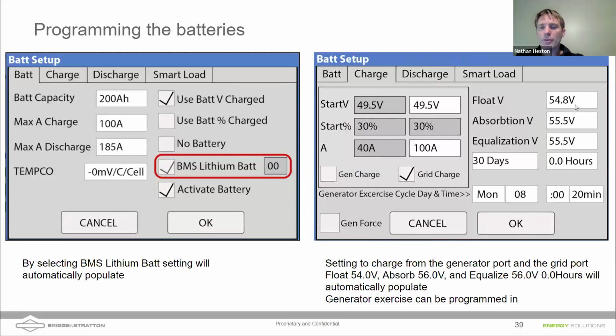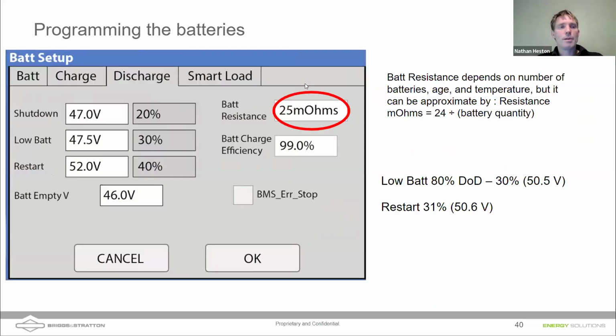Float for our batteries should be 54, absorb set to 56 volts, and equalize is something that's used for lead acid batteries, and you want to make sure that there's 0 hours there for equalization. Again, with communicating batteries, they'll program themselves. The discharge, you can set here. Here's a shutdown voltage. This is the low battery cutout voltage at which we will stop the output from batteries from the inverter. So this is done to protect the batteries. This should automatically set to 48 volts for our batteries.